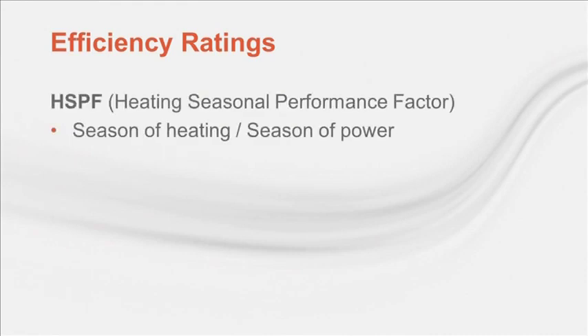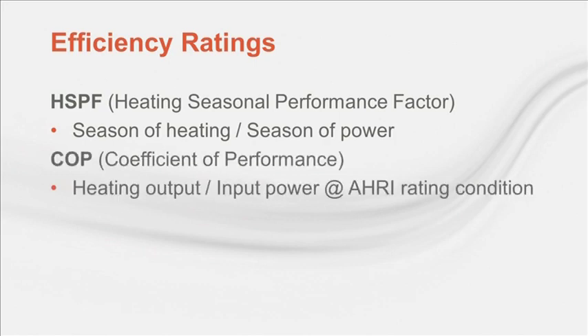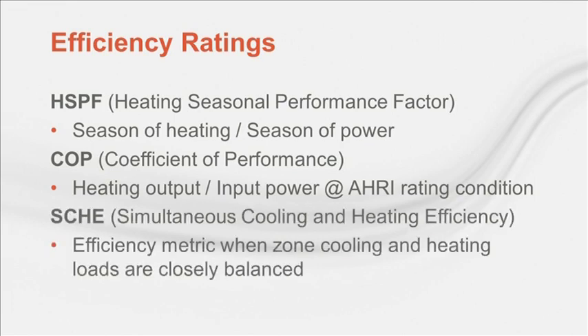On the heating side, HSPF is basically the heating equivalent of SEER and is an attempt to encompass both full load and part load heating operation. COP is the ratio of heating output at AHRI rating conditions divided by the power consumed. A unique term for VRF systems is SCHE, which is the simultaneous cooling and heating efficiency. It's included in the AHRI rating standard 1230, but it's not included in 90.1.